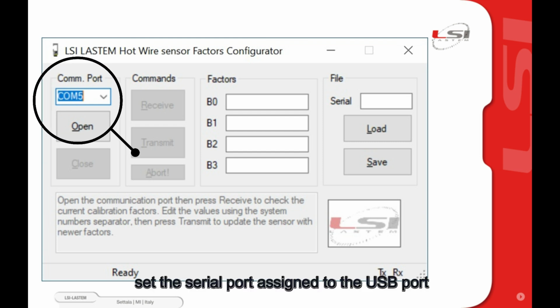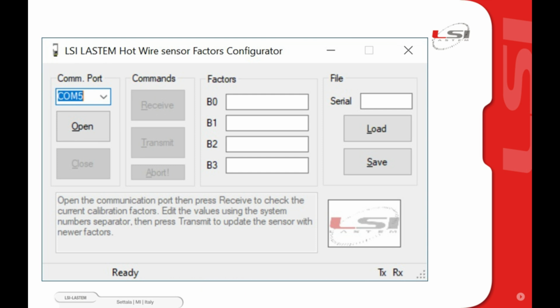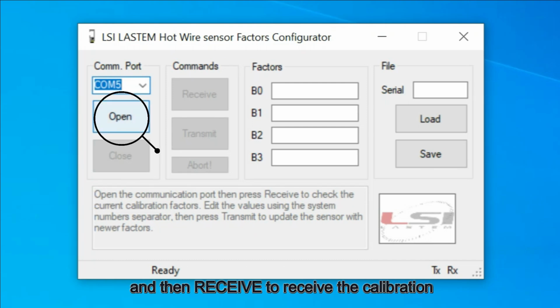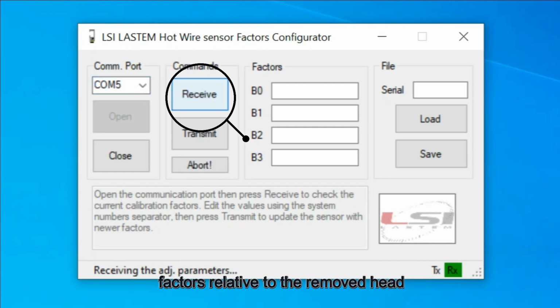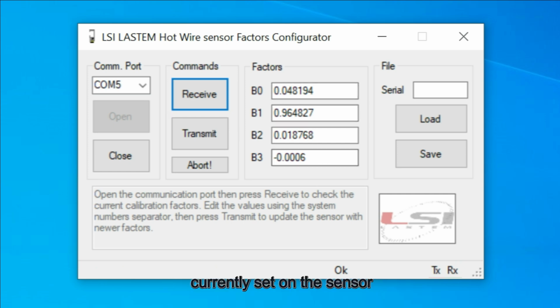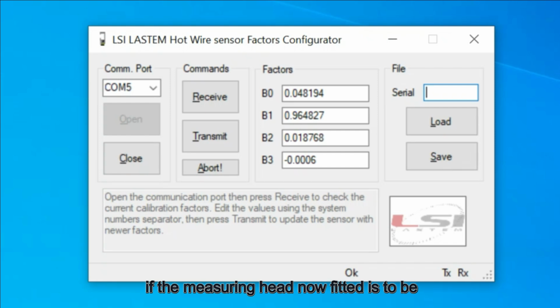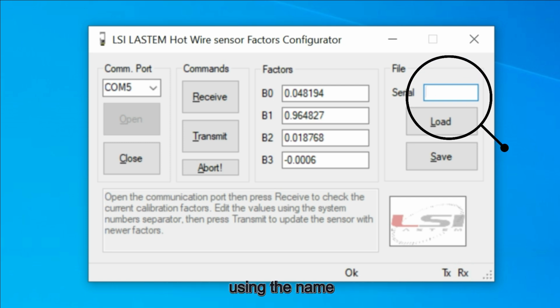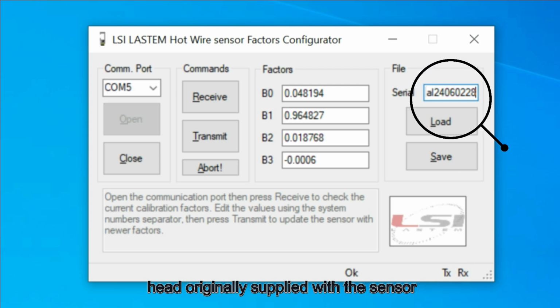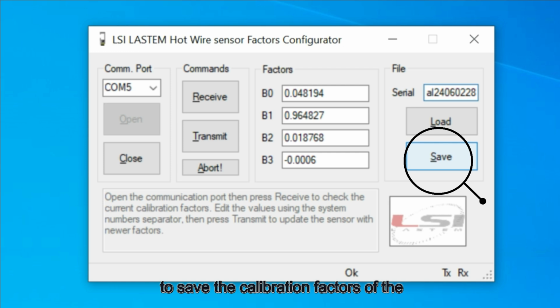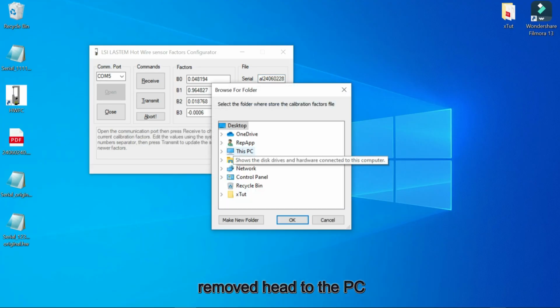Set the serial port assigned to the USB port connected to the cable. Press Open, and then Receive, to receive the calibration factors, relative to the removed head, currently set on the sensor. If the measuring head now fitted is to be reused, and was originally supplied with the sensor, enter the serial number of the anemometer sensor, using the name Original, in the serial box. This serves to identify that these calibration factors relate to the measuring head originally supplied with the sensor. Press Save, to save the calibration factors of the removed head to the PC.